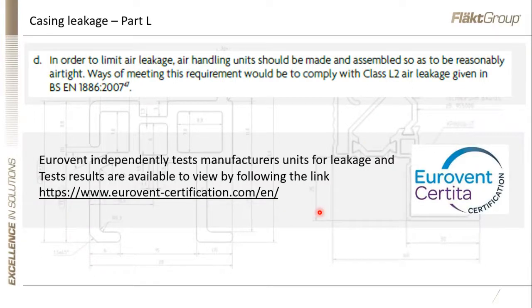Eurovent independently tests manufacturers' units for leakage, and test results are available to view by going onto the Eurovent certification webpage. So any manufacturer that is Eurovent certified has had to submit their equipment for independent testing by Eurovent, and then Eurovent publish those criteria, those definitions on their website. So if you want to know precisely how much an air handling unit leaks by, you can go to Eurovent for independent verification. The vast majority of manufacturers in the UK are not Eurovent certified, and therefore there's no independent body that you can go to verify that the manufacturer's claimed leakages are correct.